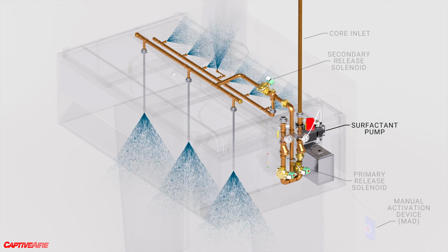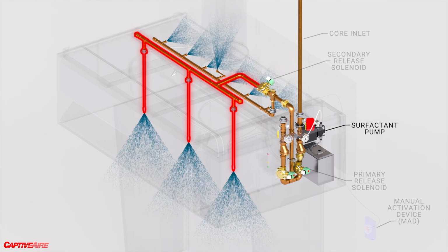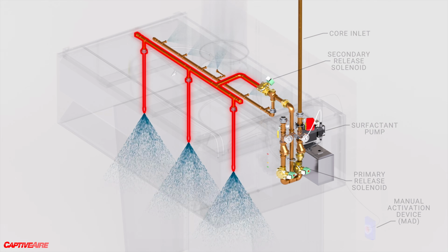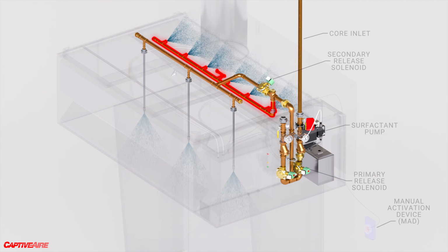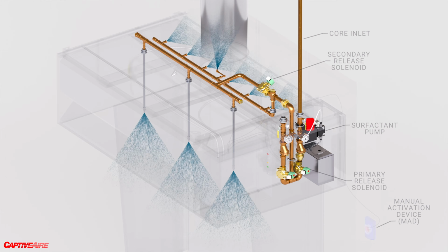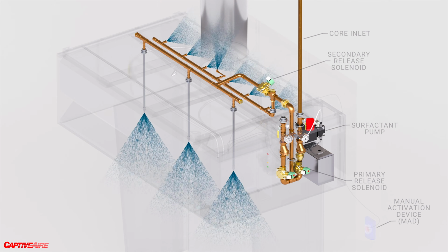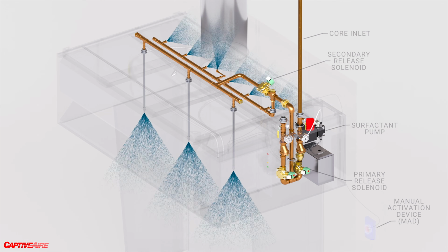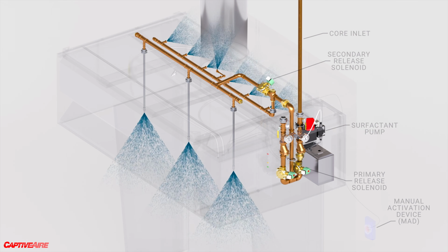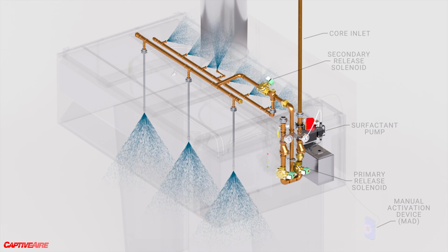The flow is then split between two manifolds. One sprays the appliances underneath the hood, while the other sprays the hood plenum and up into the ductwork. This flow will continue unless manually stopped for 15 minutes, and if after 15 minutes a fire condition is still detected, it will continue on for another 15 minutes, repeating this cycle until the fire is fully extinguished.